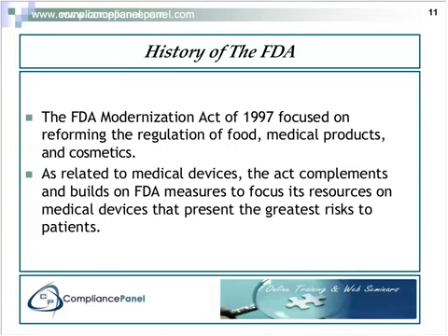The law also expanded an ongoing pilot program, which I spoke of earlier, which implemented third-party experts to conduct an initial review of Class 1 and low to intermediate risk Class 2 devices. This act, however, specified that an accredited person may not review devices that are permanently implantable. So they limit who can review these devices as a third party to those Class 1 and Class 2 devices.